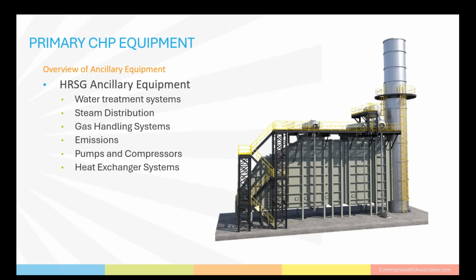regulator. This list may not be exhaustive, and specific equipment might vary depending on the HRSG design, fuel type, and CHP system requirements. But some of the basic ancillary equipment that may be required are water softeners, filters, pumps, steam traps, steam meters, pressure reducing stations, gas meters, regulators, and filters. This might also have selective catalytic reduction systems, electrostatic precipitators, gas stack analyzers. There could be feed water pumps, circulating pumps, condensate pumps, and air compressors.